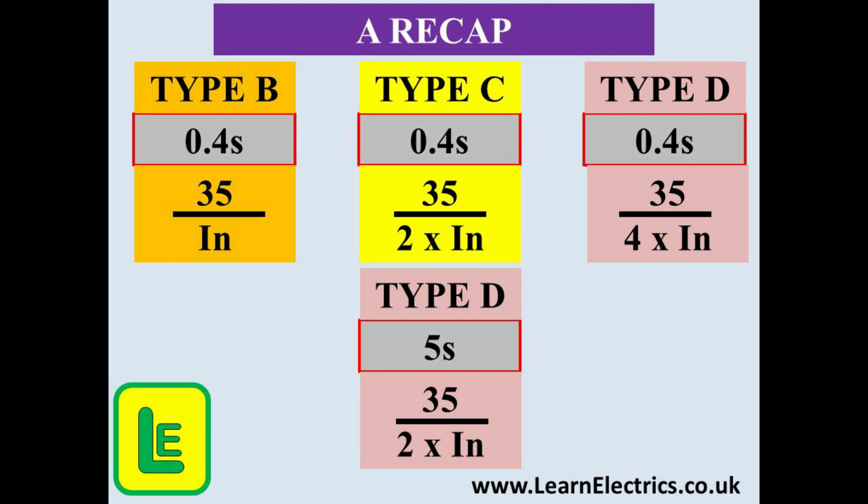That is how simple this formula is. If you are ever on site without your books and you can remember the number 35 then you can save the day. So a quick recap on this page. For a 0.4 second disconnection time and a type B breaker use the formula 35 divided by IN. And for 0.4 seconds under type C it is 35 divided by 2 times IN. Then we saw a type D breaker with a 5 second disconnection time and again it was 35 divided by 2 times IN. And finally for a type D with a 0.4 second disconnection time we used 35 divided by 4 times IN. Practice, practice, practice. Once you have learnt it you will have another powerful tool in your mental toolbox.